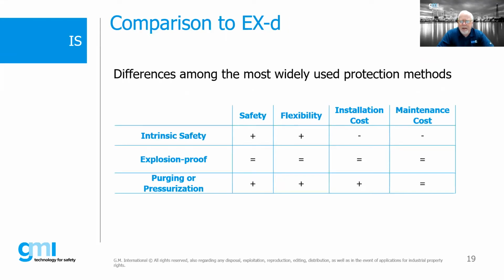This talks a little bit about safety, flexibility, installation cost, and maintenance cost. Again, intrinsic safety is one of the safest concepts out there. Purging and pressurizing is very safe, certainly. Explosion proof, when properly done, is certainly safe. The issue with explosion proof or flame proof is typically the maintenance or damage to potential flame-proof products. If we don't treat them very carefully, we sometimes have issues, and when we do inspections, we see an awful lot of issues with flame-proof or explosion-proof equipment.